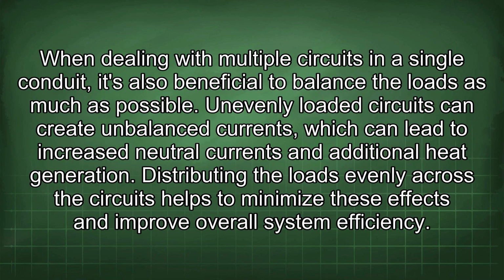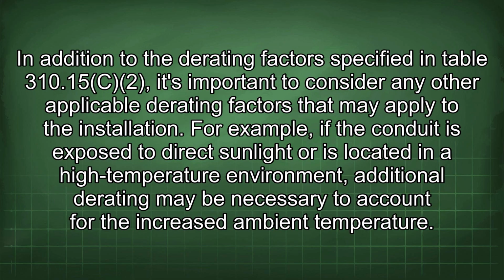When dealing with multiple circuits in a single conduit, it's also beneficial to balance the loads as much as possible. Unevenly loaded circuits can create unbalanced currents, which can lead to increased neutral currents and additional heat generation. Distributing the loads evenly across the circuits helps to minimize these effects and improve overall system efficiency. In addition to the derating factors specified in Table 310.15c2, it's important to consider any other applicable derating factors that may apply to the installation.